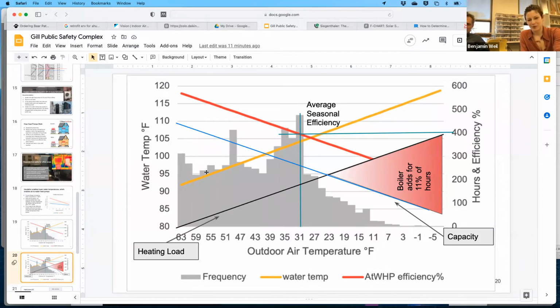So now we're getting even more mathematical. This blue line represents the capacity of the heat pump to extract heat from the outdoor air. And you can see how that goes down as the outdoor air temperature decreases. And this black line represents, as the temperature decreases, the heating load increases. And eventually, at some point, the need to add heat into the space will surpass the ability of the heat pump to add heat into the space. And that's where the boiler comes in as a backup.